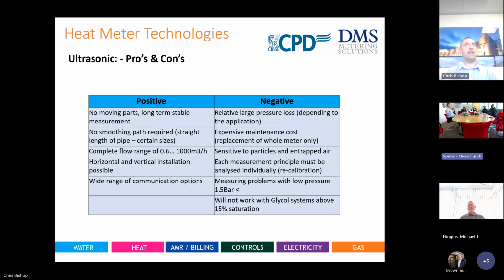So you've also got that mentality: if it's a mechanical meter installed in a HIU, where buildings generally are going up now, then you're installing that mechanical meter vertically, naturally, without even recognizing it. So it's another design parameter to keep in mind for the more expensive manufactured brands out there. The long-term accuracy and the capture of data is what it's all about. And then obviously wide communication options. All the high profile manufacturers now have a lot of unique data collection methods: sometimes a mobile phone, a website portal, a cloud-based platform, billing invoices. You're not limited now in how you get your data.